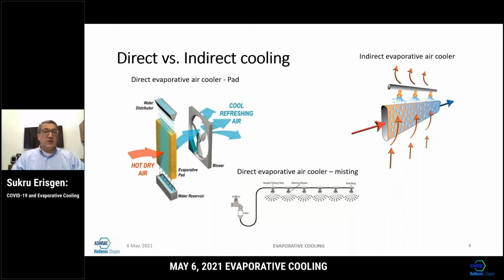The most common and known are wetted media, a media that looks like corrugated cardboard. You soak it with water using a water distributor on top, you drip water, and the hot air enters. You move the air using a fan, and cool fresh air comes out from the other side, typically at very high relative humidity ratios. Excess water is collected at the bottom; sometimes it is recirculated, sometimes drained to control the mineral content.